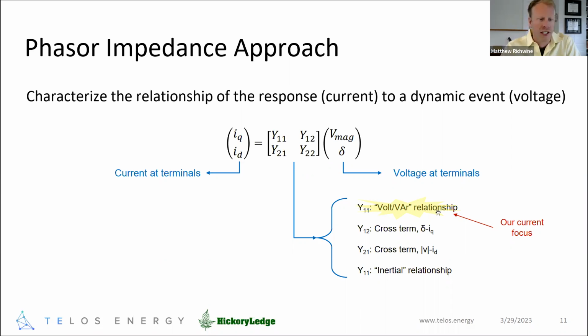Y11 is essentially the relationship between reactive current and voltage magnitude, and this is really the focus of what I'll share today. It's the volt-var relationship: when voltage magnitude changes, you expect a response in reactive current. For instance, if voltage suddenly drops due to some change on the grid, you'd expect a voltage-supporting response to try to restore voltage, meaning an injection of reactive power and consequently reactive current, or the conjugate of that.